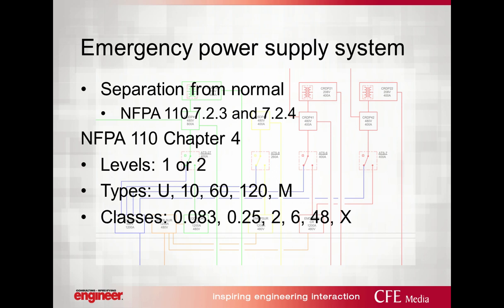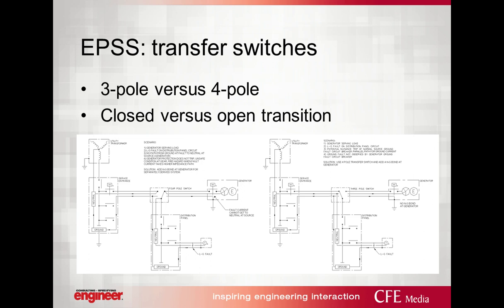Now, which one are you going to fall under? Again, you're going to be doing your risk assessment and following both the NEC and NFPA. Now, the class is the runtime in hours. So how long does it have to run? In healthcare applications and seismic zones, class X might even be 96 hours. So you're going to coordinate this with your AHJ to determine what you actually have to do for each one of your EPSS selections.